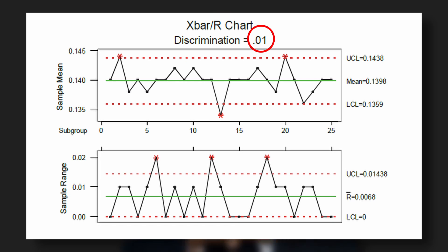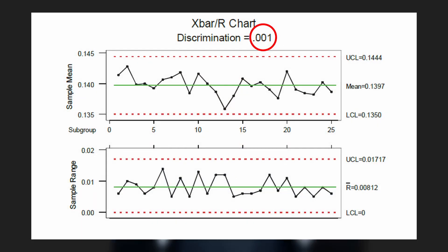Let's take an example. If you look at the graph, there was an instrument with a least count of 0.01 mm. On the range chart, you will find 3 points going out of the upper control limit. Now if you do the same test using a different instrument with a least count of 0.001 mm, all the points are within the control limit.